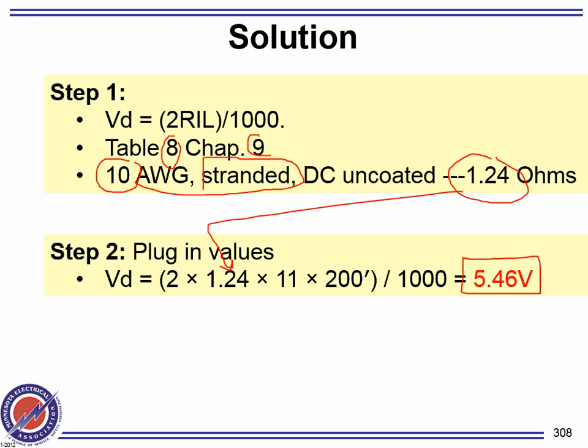That's your default. Unless you know otherwise, you always default to uncoated copper. They used to coat the copper in the past to protect it from the elements. They don't do it anymore unless they tell you it's coated. Does that make sense? But don't forget solid and stranded, because the guys up to, what is it, number 10, I think, have solid and stranded, or did they go to 8? Yeah, table 8. They have solid 8. After that everything is stranded.